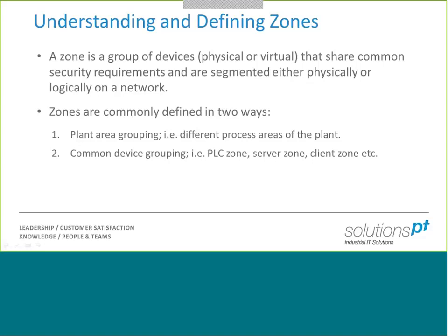What I mean by that is if we only had a small handful of PLCs, servers, and workstations, for example, we may define a zone for each one of those. So a zone for our PLCs, a zone for our servers, a zone for our clients. Now, as I say, there's no straight answer to this question. It is the hardest part about defining the zones and understanding them. So it has to be approached on a case-by-case basis, but these are just two starting points for people to look at when defining them.